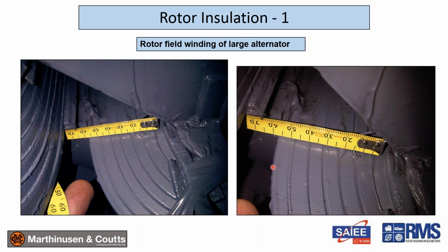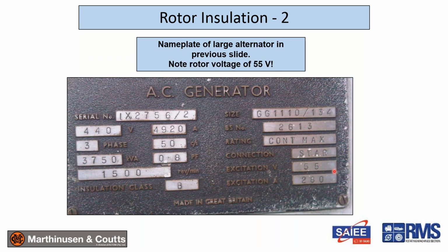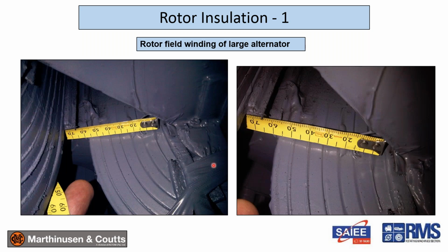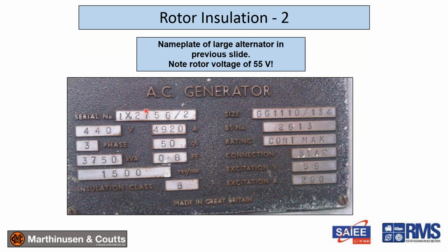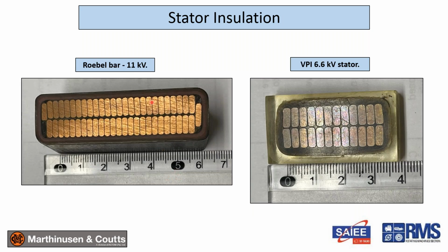And the nameplate of that machine, just to give you an idea, quite an old machine, a 3.7 MVA. But what's interesting about it is look at that excitation voltage. That coil only sits at 55 volts, and yet remember that this is the turn insulation. The flanges, so the main insulators from the pole body, are much thicker. And again, the mechanical implications totally override electrical considerations.